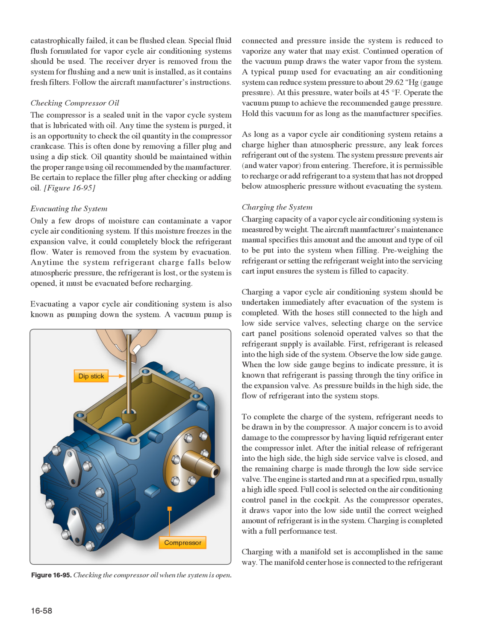Anytime the system is purged, it is an opportunity to check the oil quantity in the compressor crankcase. This is often done by removing a filler plug and using a dipstick. Oil quantity should be maintained within the proper range using oil recommended by the manufacturer. Be certain to replace the filler plug after checking or adding oil. Figure 1695, evacuating the system.